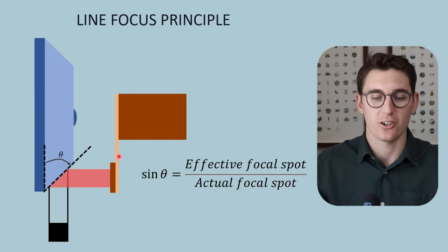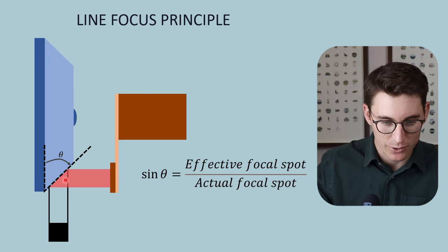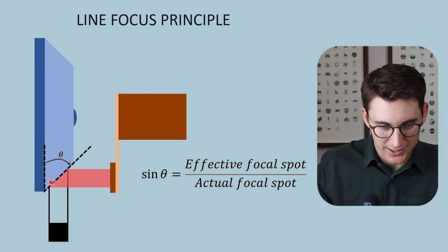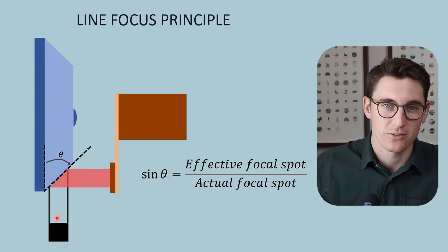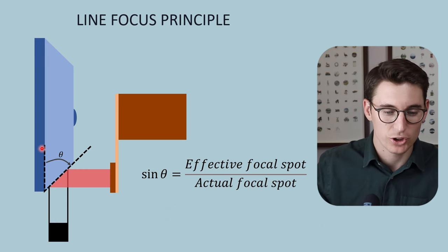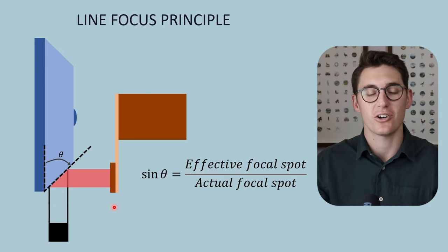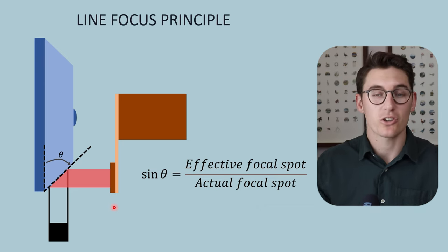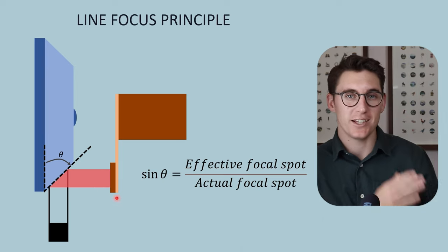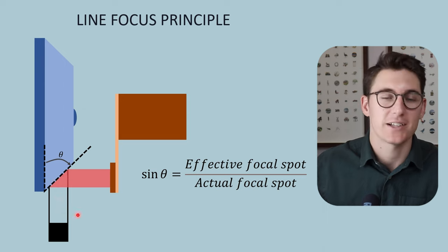Looking at this from side on in a simplified 2D diagram: we have the cathode, the electron beam, and where the electron beam contacts the anode is the actual focal spot, with the effective focal spot heading off towards the patient. The anode angle changes our effective focal spot, and there's a way we can calculate that which is known as the line focus principle. The line focus principle shows us the relationship in the longitudinal direction between our anode angle and our actual and effective focal spots.